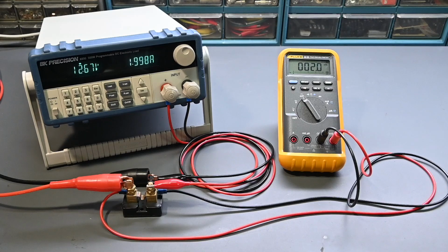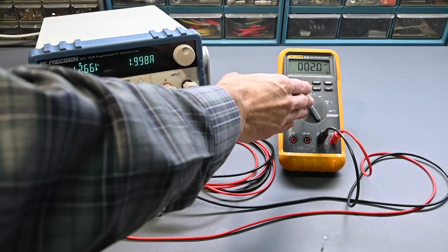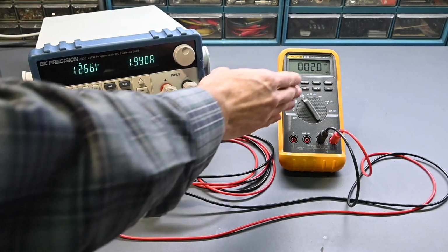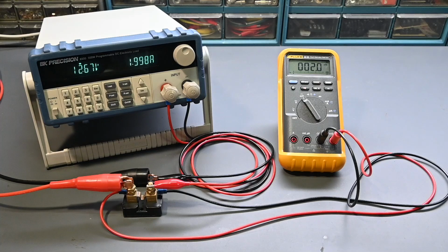But you do have to have an appropriate voltmeter to measure the voltage that this shunt is creating. So you can see it's a very small value, just 2 millivolts. So of course the meter needs to be able to detect that. And if you're measuring DC current, then this is measuring DC volts. If this is AC current, then you're measuring AC volts. So depending on the shunt resistance, it can be made for extremely low or up to extremely high currents.